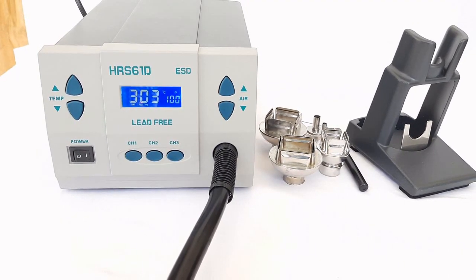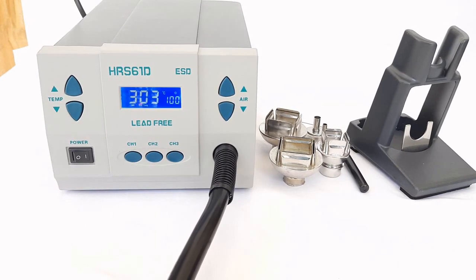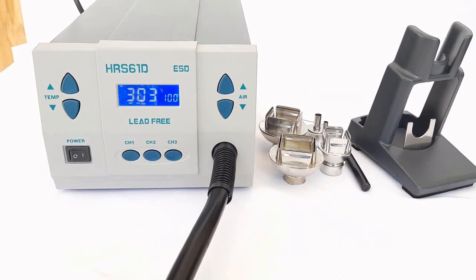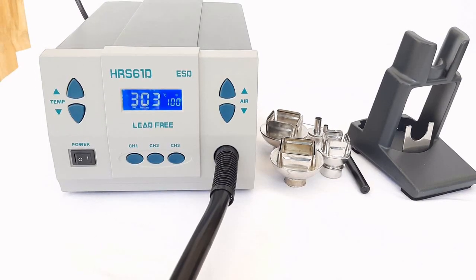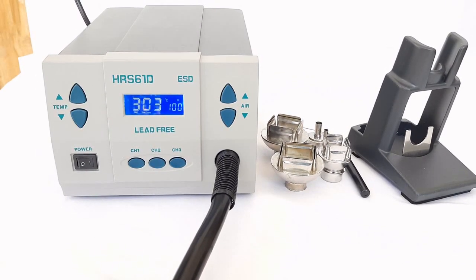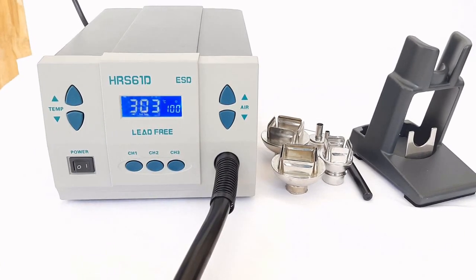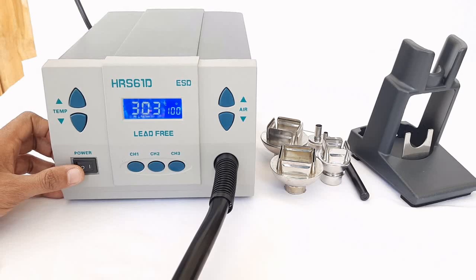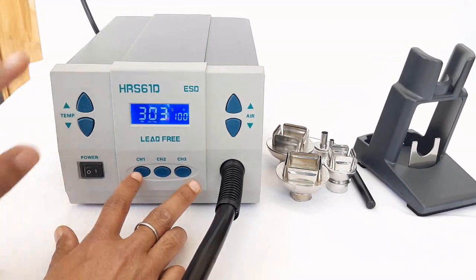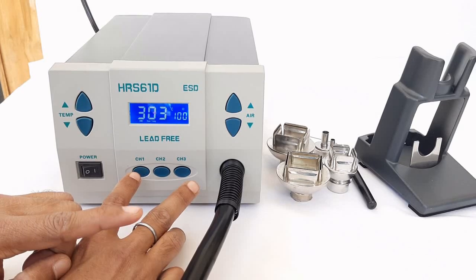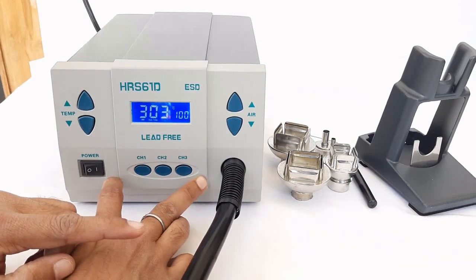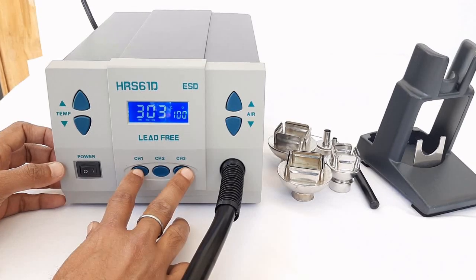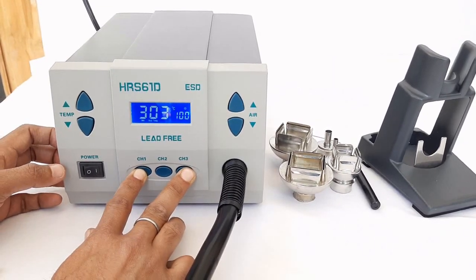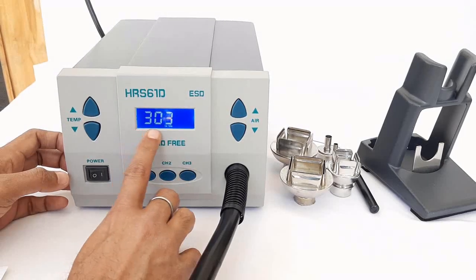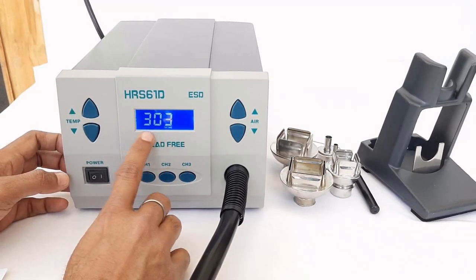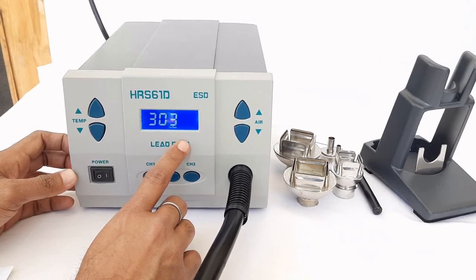So all we need to do is first check the actual temperature with the help of an external calibrator. Then if any deviation is observed, we can alter the temperature setting here. All we need to do is, in the on state, and if the locking is disabled, press channel 1 and channel 3 simultaneously for 15 seconds. Then the system will enter calibration mode. Then we just enter the value which we have observed on the external calibrator.